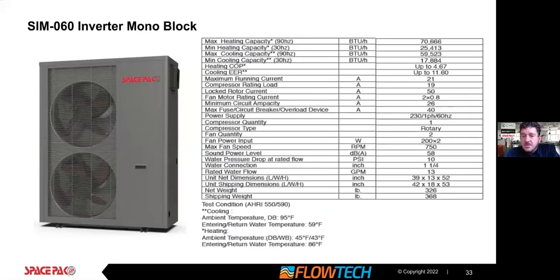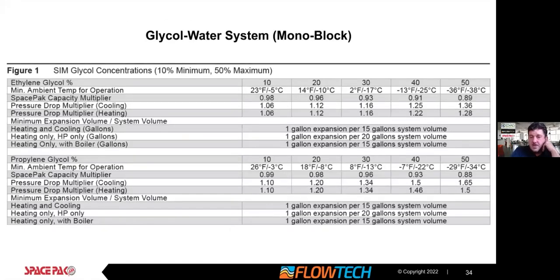The pressure drop is much higher. This unit has a pressure drop of 23 feet of head at 13 gallons a minute just through the unit itself. So that is quite big, so we're going to make sure to pay attention to that. A little mention on the glycol.